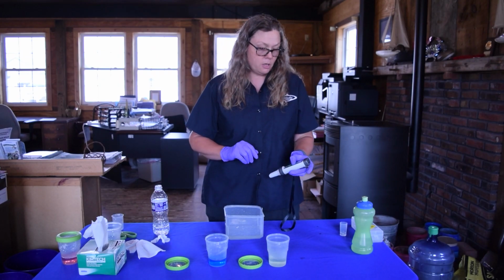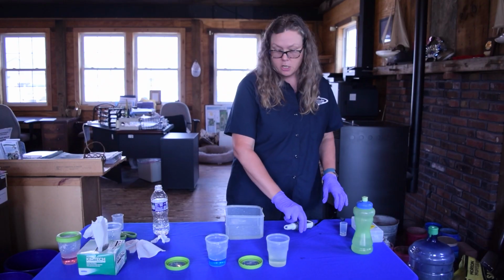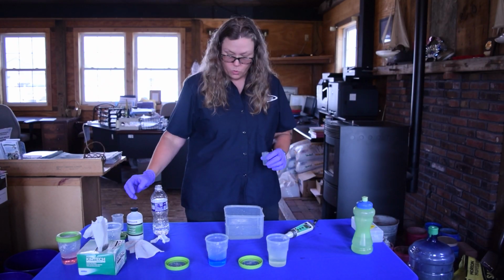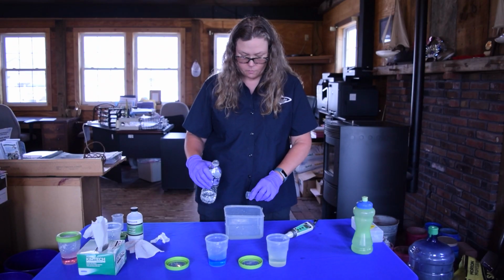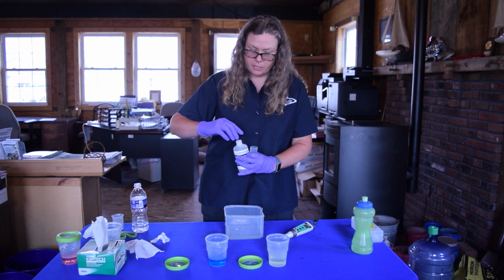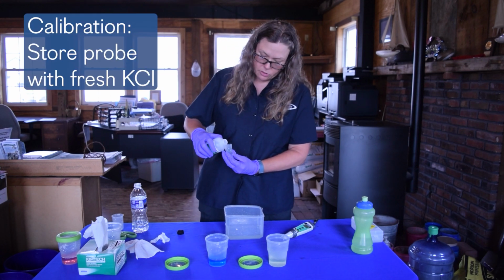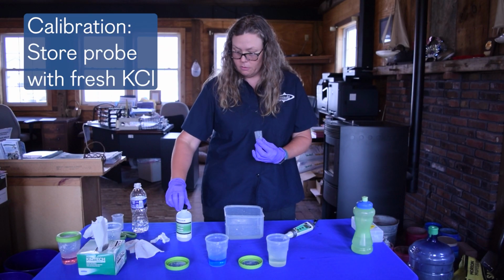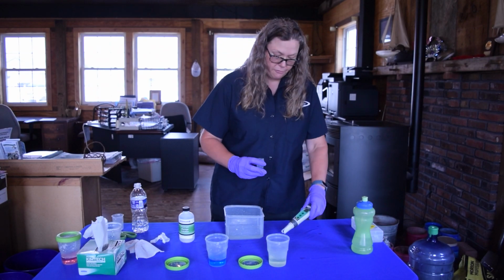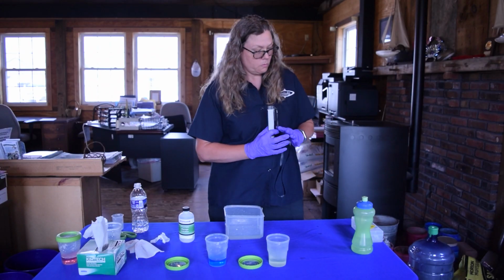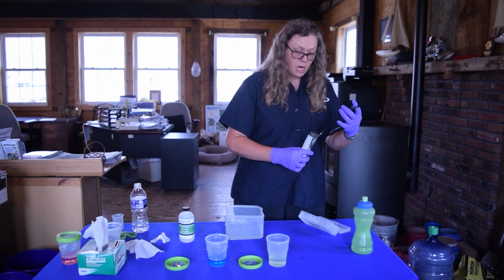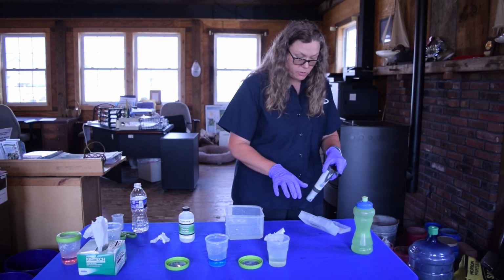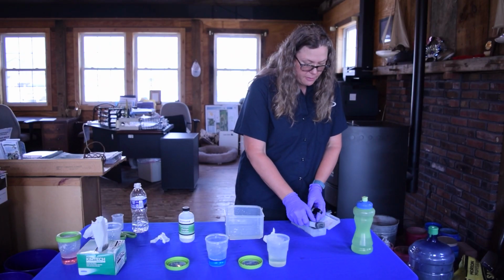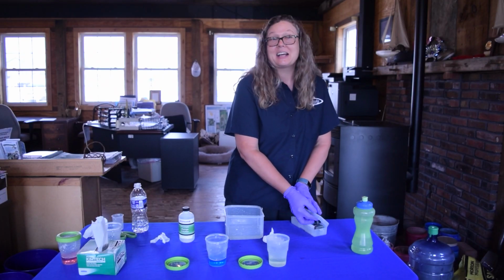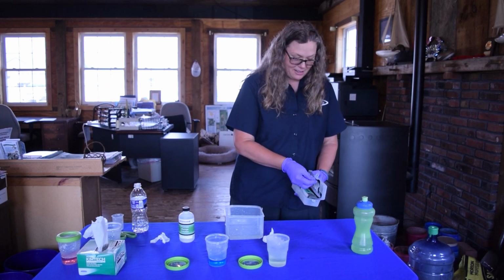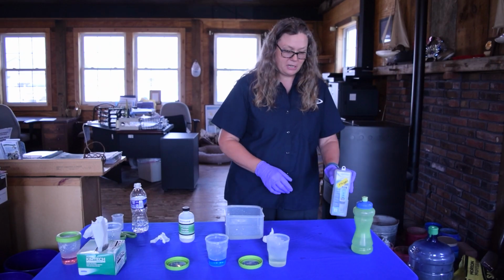We can turn off the instrument with a long press or just let it turn off itself. And lastly, we want to just rinse out the cap really quickly. And then we're just going to add some fresh KCl. Again, we have this nifty little fill line. So it shows you exactly how high up the KCl should come. Fill it with fresh, recap it, and you can place it back into its storage case. We do recommend that you store it upright in between sampling periods. And again, you're going to put your pH meter with your other instruments in a climate-controlled, cool, dark place until the next sampling period.